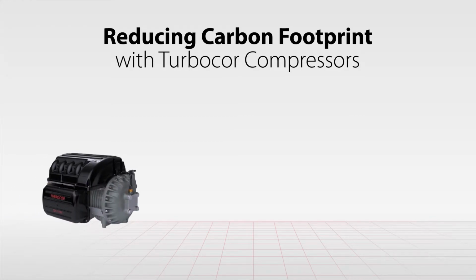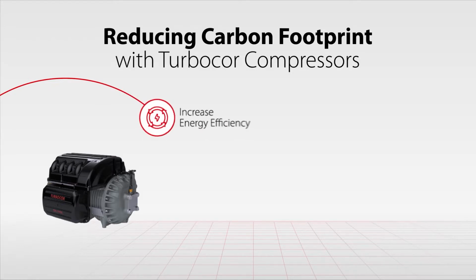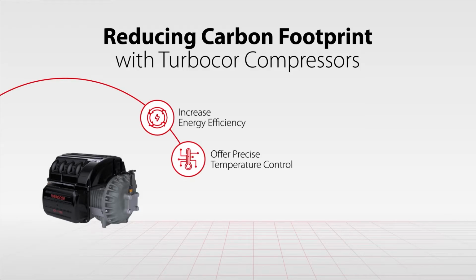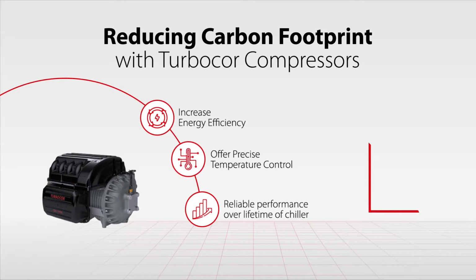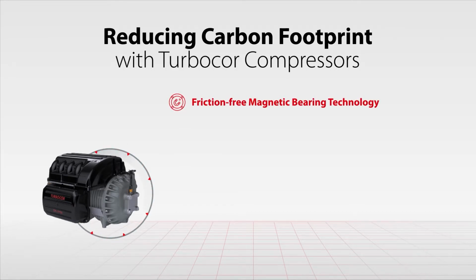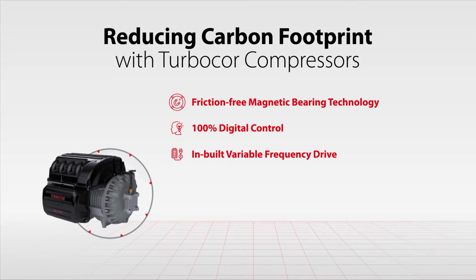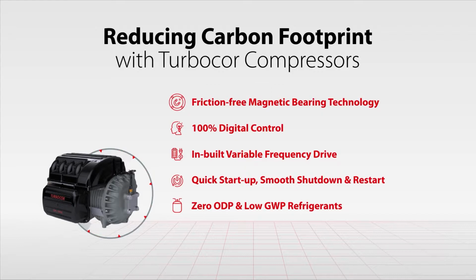Danfoss Turbocor compressors play an invaluable part in reducing carbon footprint of a data center by impressively increasing energy efficiency. They offer precise temperature control and reliable performance over the lifetime of the chiller and provide 40% higher IPLV than conventional systems, which can help chillers achieve the Bureau of Energy Efficiency's 5-star rating. Turbocor's friction-free magnetic bearing technology ensures zero drop in chiller performance. The compressor offers multiple advantages, including intuitive operation with 100% digital control and up to 50% lower energy consumption with inbuilt variable frequency drive. Its quick startup, smooth shutdown and restart ensure uninterrupted cooling and higher system security. Turbocor is optimized for the zero ozone depletion potential refrigerant, HFC-134A, and is future ready for low GWP and ultra low GWP refrigerants.